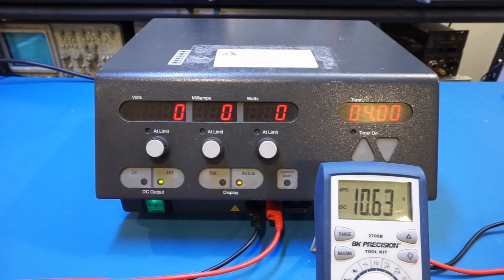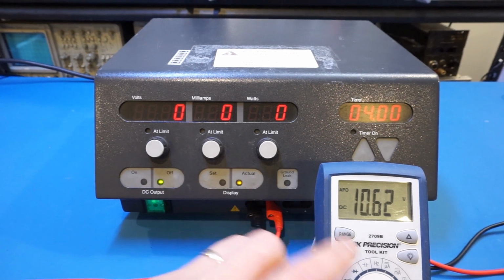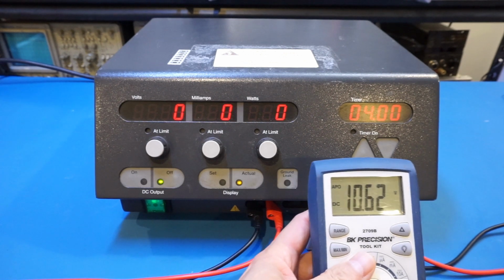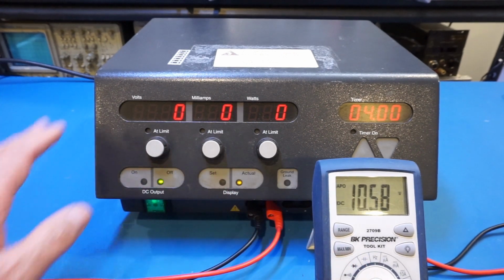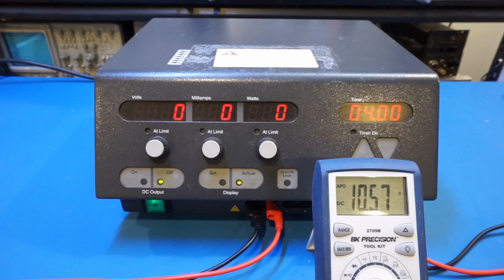Anything larger than 3 mega ohm doesn't seem to work, so I'll just leave it at 3 mega ohm. The first thing you notice is that the residual value is at 10 volts. That's quite typical because these kinds of power supplies are usually meant for much higher voltage, at least several hundred volts, so starting from 10 volts is perfectly acceptable.